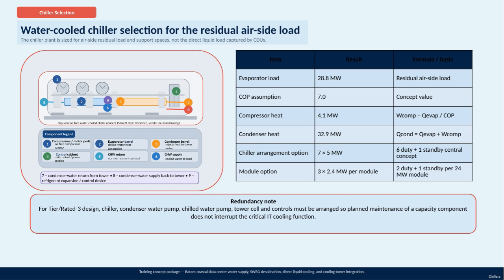For system arrangement, there are 2 options: one central plant with 7 chillers rated at 5 megawatts each, where 6 run in duty and 1 is on standby, or a modular setup with 3 modules each having 3 chillers at 2.4 megawatts, maintaining 2 duty and 1 standby per module. A critical aspect here is redundancy. For a Tier 3 or rated Tier 3 design, every component, including chillers, condenser, and chilled water pumps, tower cells, and control systems, must be configured so that planned maintenance on any one part doesn't disrupt the overall critical IT cooling function.